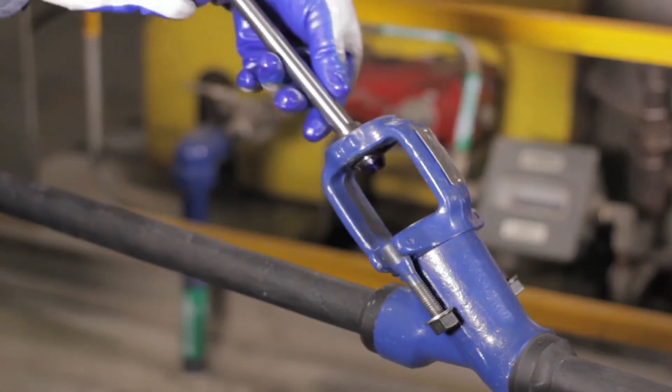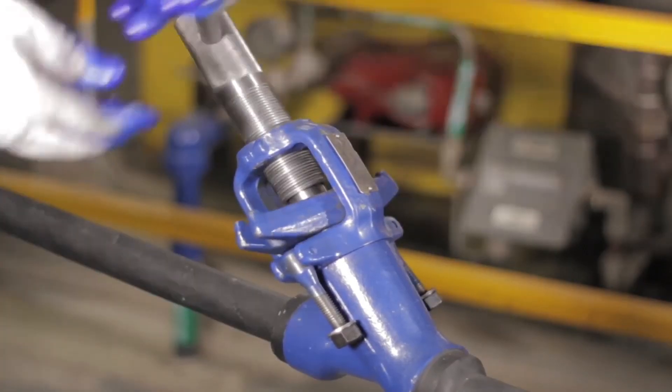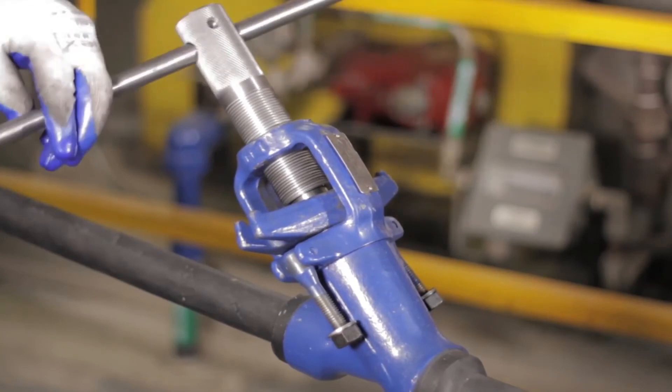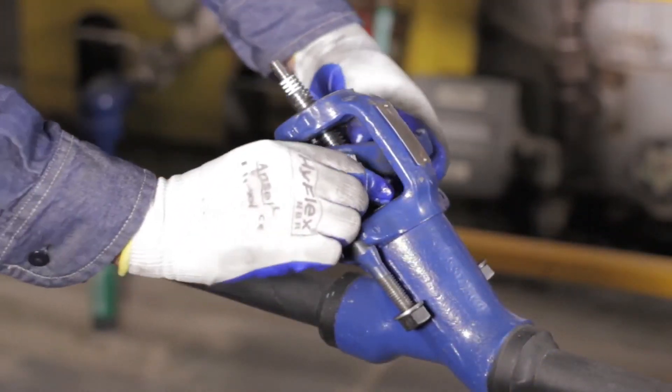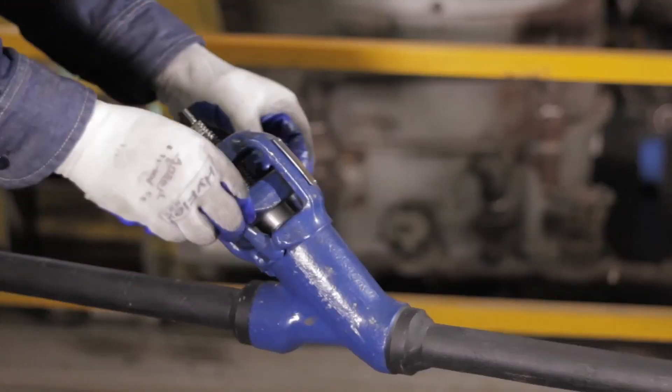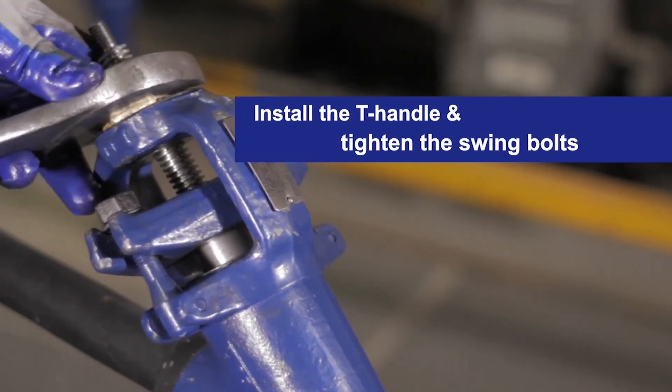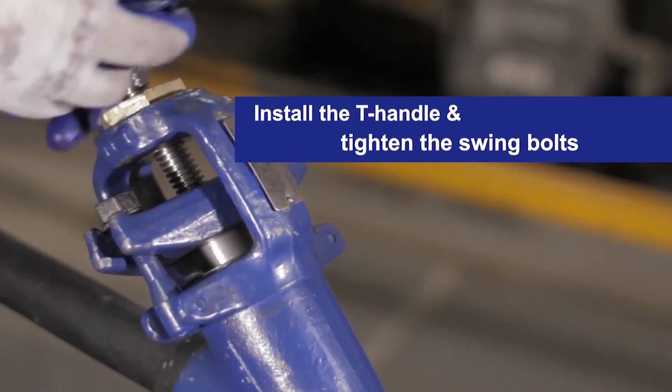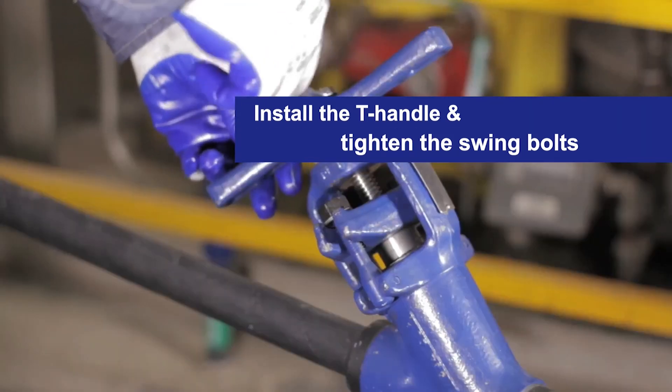For fixed backseat designs, the procedure goes like this. Insert the stem and disc assembly. Using the backseat removal tool and the guide, thread the backseat and tighten firmly. Remove the backseat removal tool and drop in the packing support ring. Install new packing. Insert the split gland bushing and turn it 90 degrees. Position the swing bolts and tighten the yoke bushing. Pin or re-tack the yoke bushing. Install the T-handle and tighten the swing bolts.